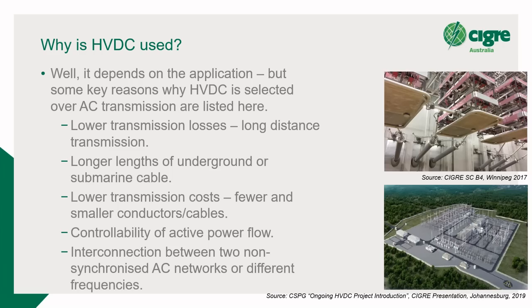The third one is lower transmission costs. So, stating the obvious, if it's a bipole system or a symmetric monopole system, there are only two conductors or two cables rather than three. So there's an immediate saving there. But the DC cable and lines tend to have smaller conductor sizes, lower metal costs, and the towers tend to be smaller for overhead lines. So you can actually get some good cost benefits there. Controllability of active power flow. So a converter station is more or less, you type in how many megawatts you want delivered at your connection point, and it will produce that, subject to availability at the source.